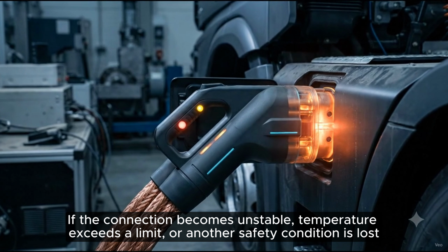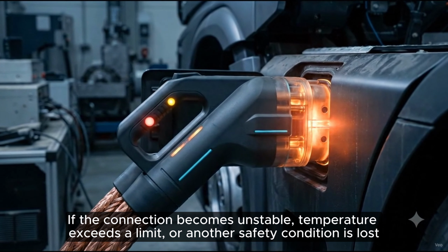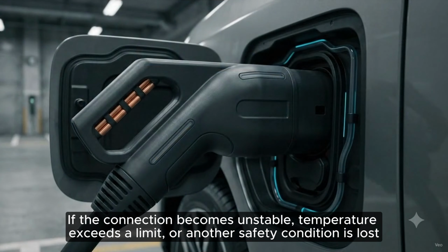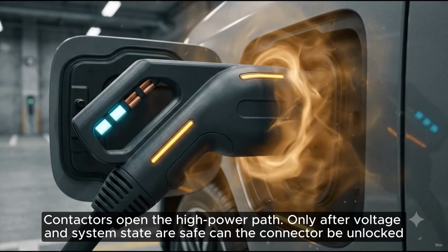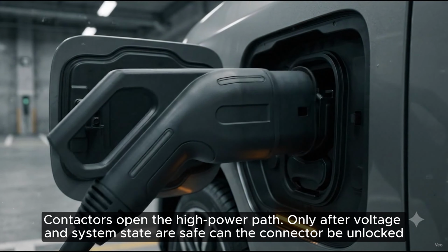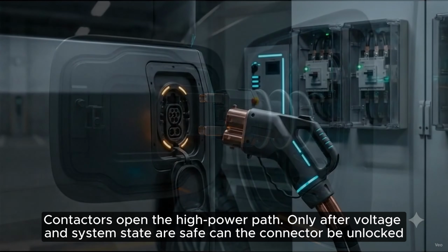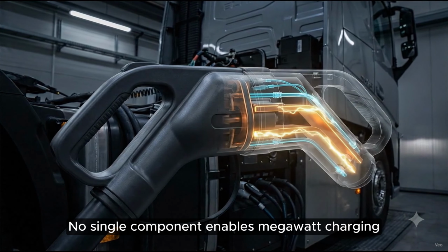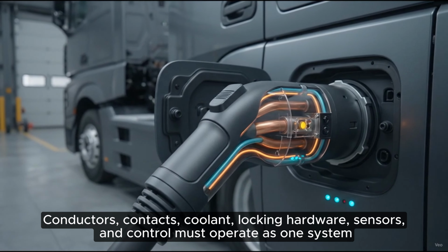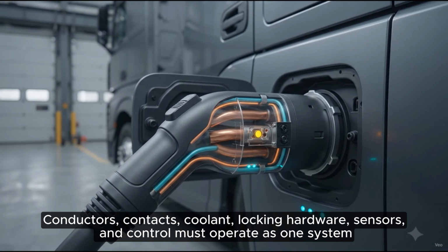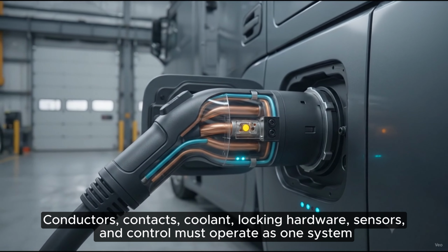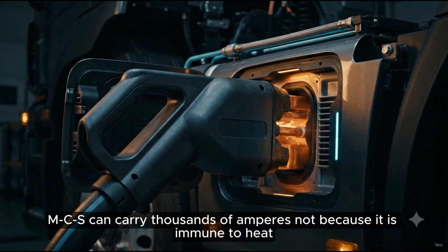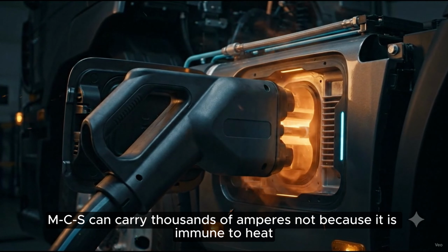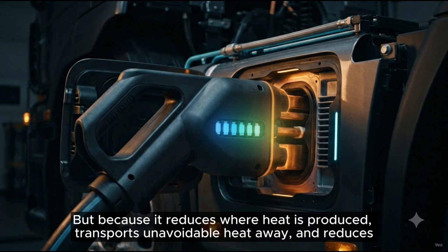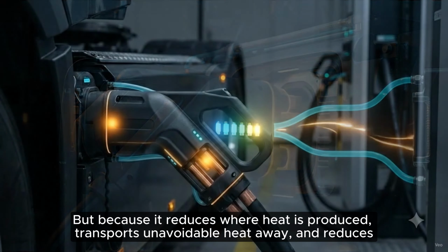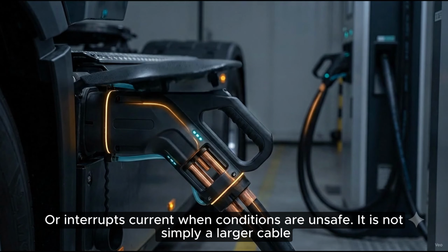If the connection becomes unstable, temperature exceeds a limit, or another safety condition is lost, contactors open the high power path. Only after voltage and system state are safe can the connector be unlocked. No single component enables megawatt charging. Conductors, contacts, coolant, locking hardware, sensors, and control must operate as one system. MCS can carry thousands of amperes not because it is immune to heat, but because it reduces where heat is produced, transports unavoidable heat away, and reduces or interrupts current when conditions are unsafe.